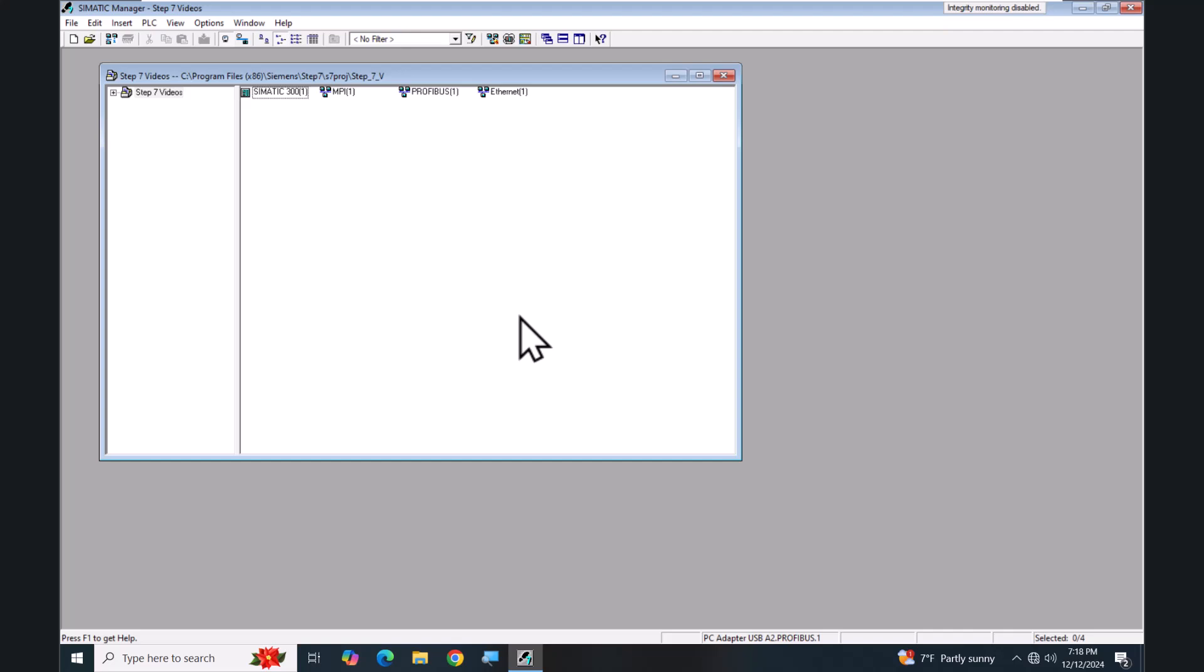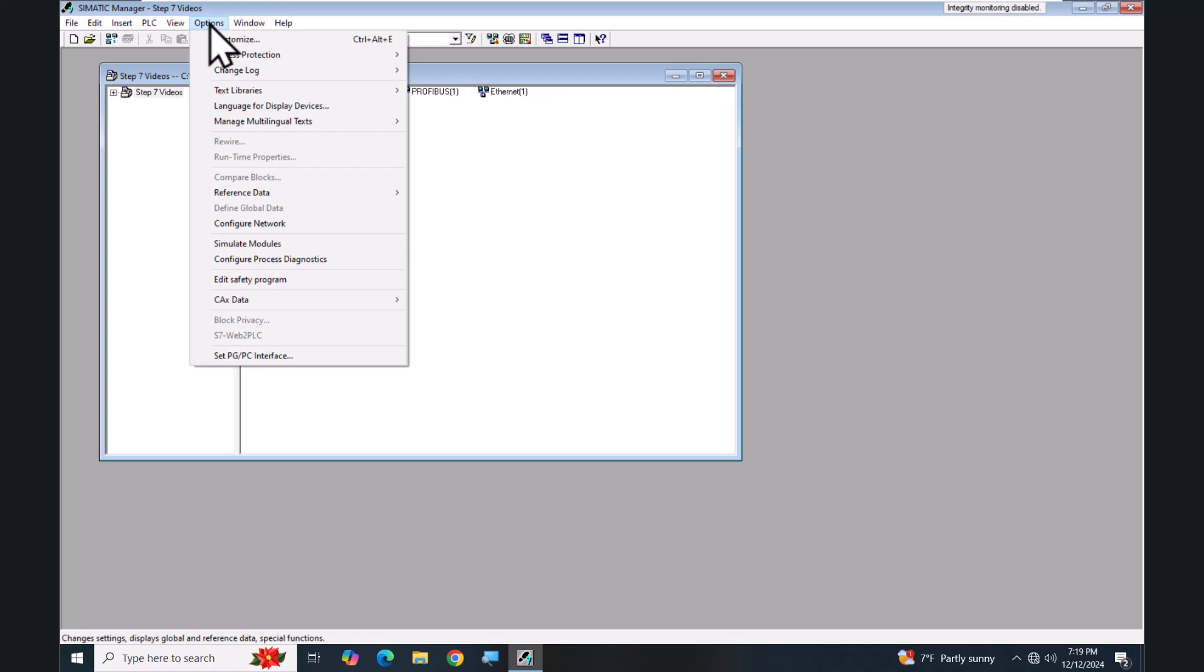In this lesson we are going to cover Set PG/PC Interface and displaying accessible nodes. The Set PG/PC interface is for configuring the physical interface that you are going to use to go online with Step 7 with your PLC. In the status bar of the SIMATIC Manager at the bottom, you can see your currently selected physical interface. Currently I am configured to go online with a PROFIBUS connection. This can be changed by going up to the Options menu and selecting Set PG/PC Interface.